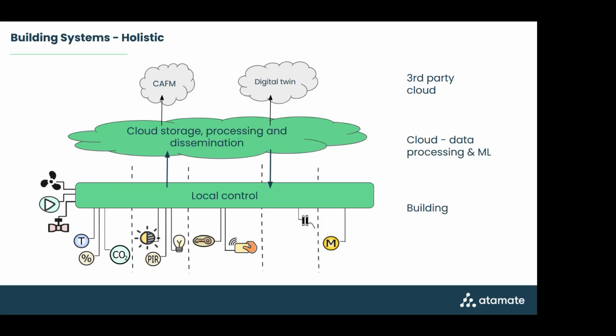To explain that - if you've got a well-designed maintenance system, taking a relatively simple example: if you click a light switch in a room, the only person who knows the lights have gone on is you. But if you've got ambient light sensors in there, when you click the switch, you can run a query on the database that says, if I see a light switch click, within 1 or 2 seconds I expect to see a change in light level. If there's no change, that can be reported into the system.